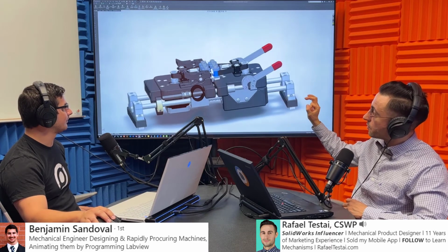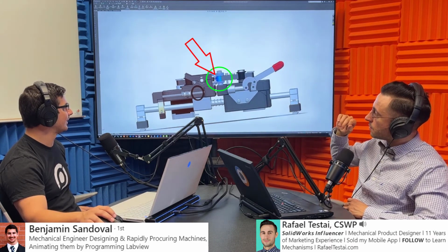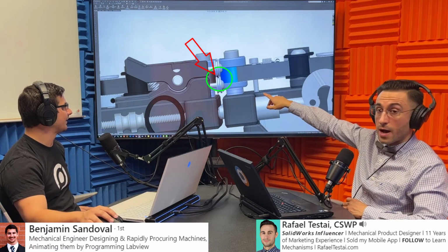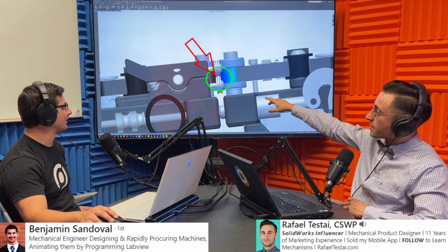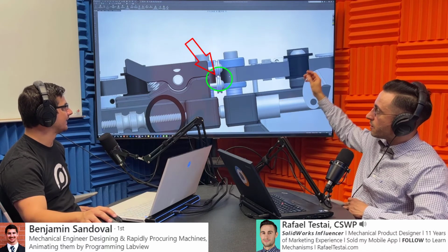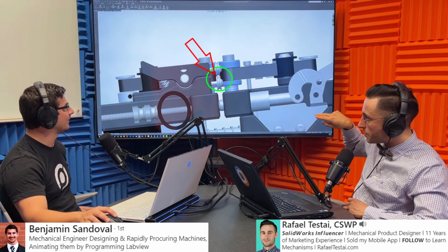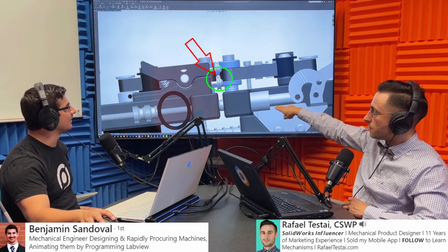So if you do the normal view from the side again, that had that small orifice we were looking at just a few moments ago, what goes in right here, as you can see where the mouse is placed, is the catheter cable. Is that right? Uh-huh. And on the other side, somewhere that's not on the screen, is a receiving end that we're going to put the catheter cable through into, right? Correct. And we want to test the friction on that, how much force it takes to get through inside of it. Exactly, and I can give you a better picture of what that looks like.